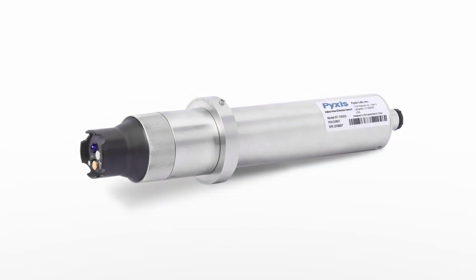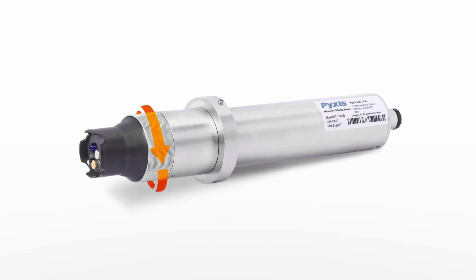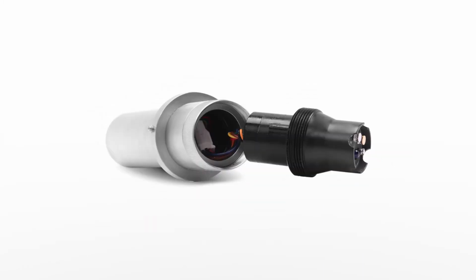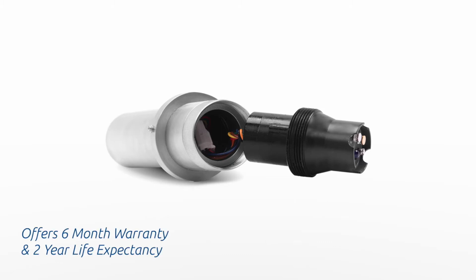This sensor series offers an easily replaceable front-loading reference electrode assembly that has been independently developed by Pyxis Lab, eliminating the shortcomings associated with membranes and gel replacement while offering reduced polarization time during sensor startup. The flat front-end design makes this platform less prone to contamination or fouling. It's easy to clean and offers a 6-month electrode assembly warranty with a 2-year life expectancy.